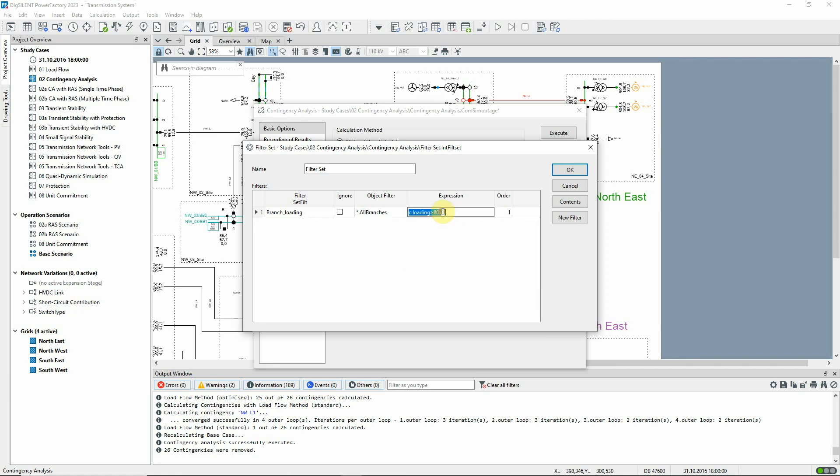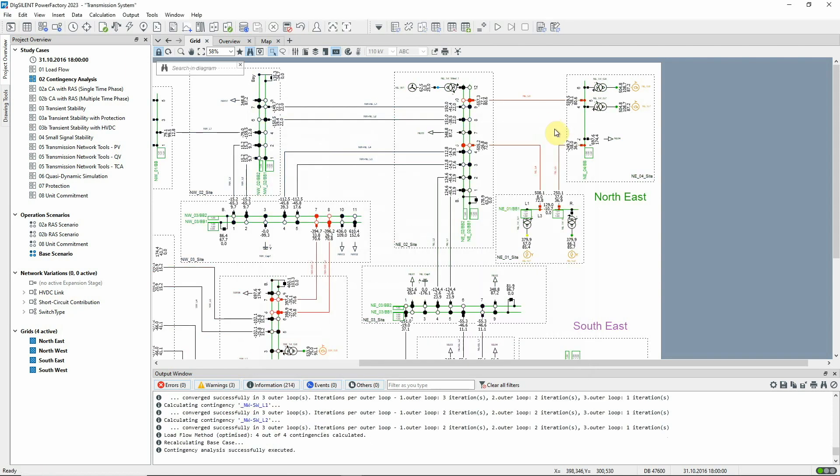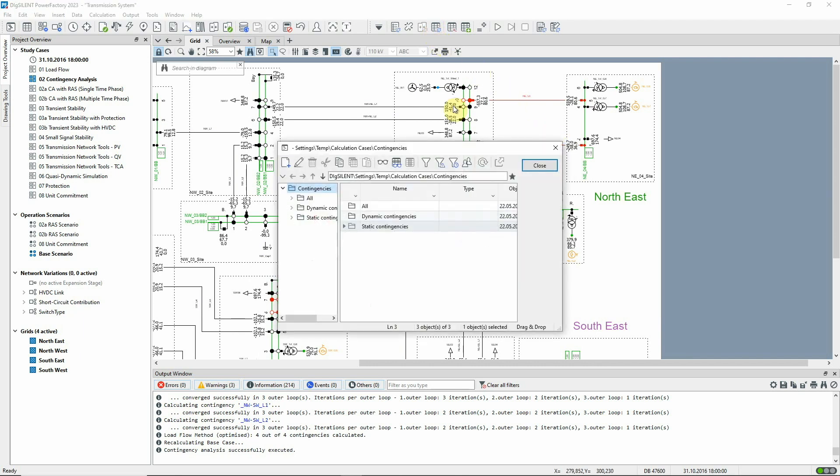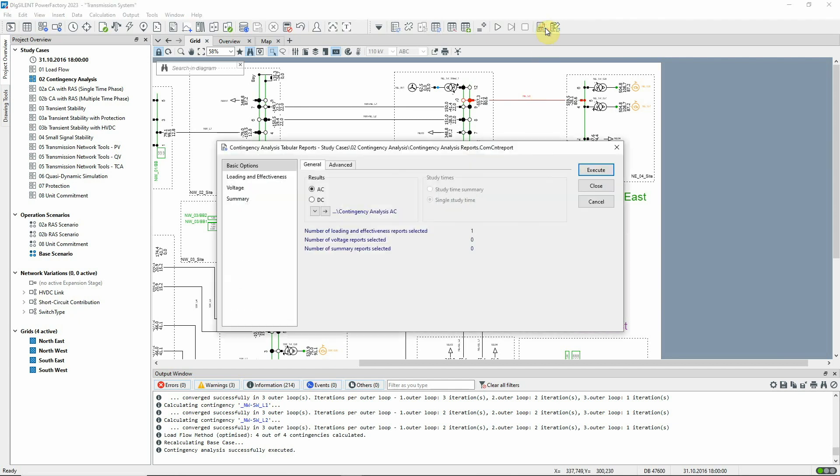We will change the default filter setting to 70. This means that a contingency will be included for any circuit loaded above 70% in the base case load flow. When the calculation has run, we can use this icon to see which contingencies have been executed, and the reports can be run as before.